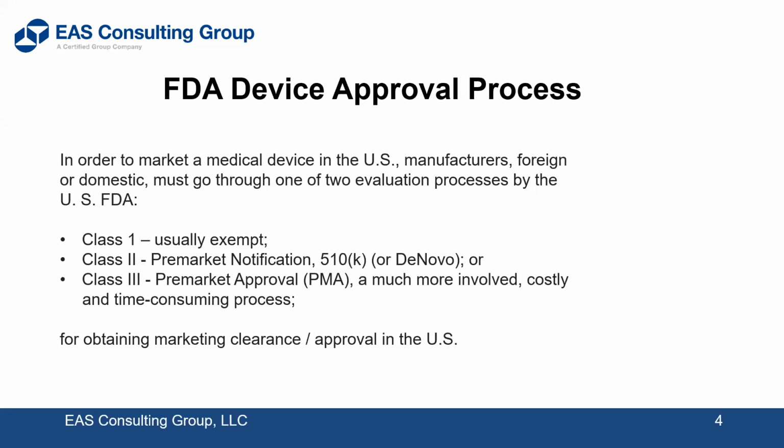Now, in most cases, the 510K does not require clinicals, but some 510Ks do, and I've worked with one that did, or was determined to require one on the part of the FDA when they started reviewing our submission. So that does happen. Now, when you're dealing with class 3 devices, those are devices you won't find listed in the 21 CFR 800. And so in most cases, they will be PMA. These are high-risk products. Almost always they require clinicals. They can take several years to get through the process, and they're extremely complex.